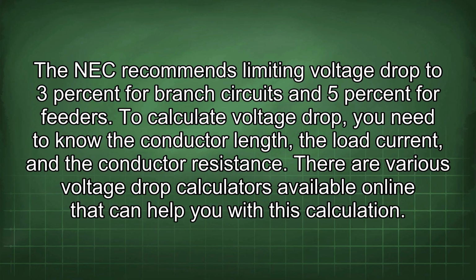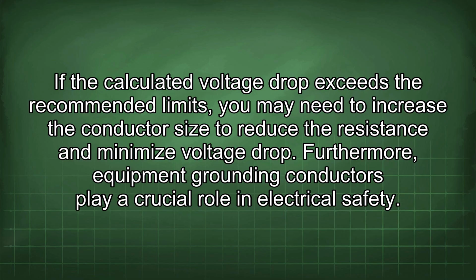To calculate voltage drop, you need to know the conductor length, the load current, and the conductor resistance. There are various voltage drop calculators available online that can help you with this calculation. If the calculated voltage drop exceeds the recommended limits, you may need to increase the conductor size to reduce the resistance and minimize voltage drop.